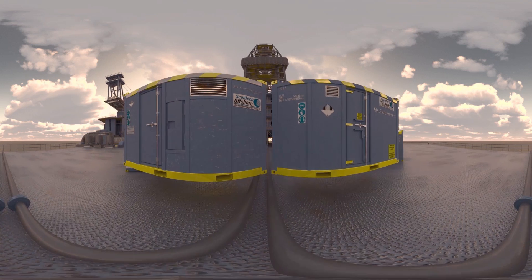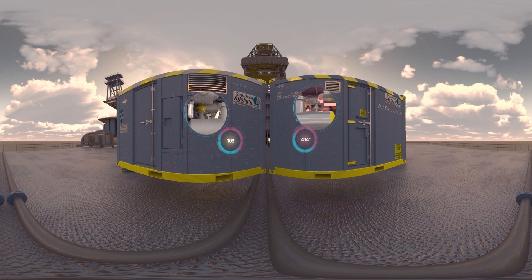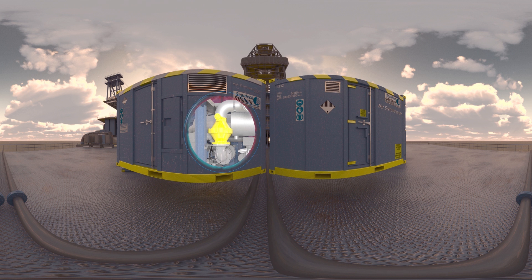Following shutdown, rig-safe surface temperatures remain above the auto-ignition point of hydrocarbons for many minutes. Zone 2 equipment employs proprietary fail-safe components that isolate potential flame paths to engine and atmosphere. Rig-safe equipment has none, increasing the chance of ignition.